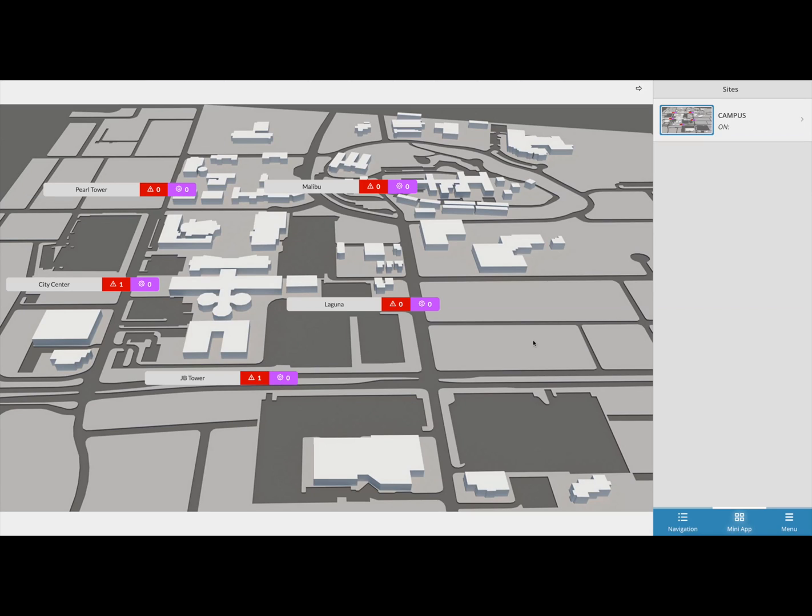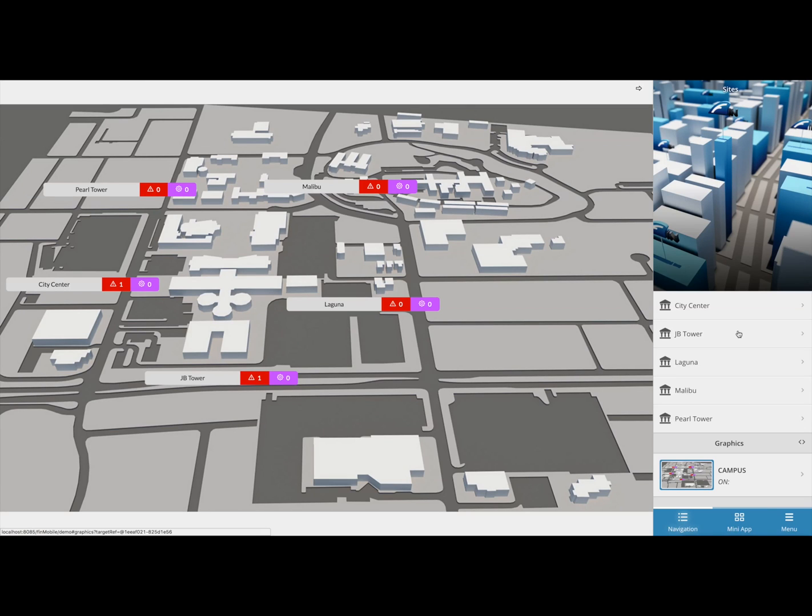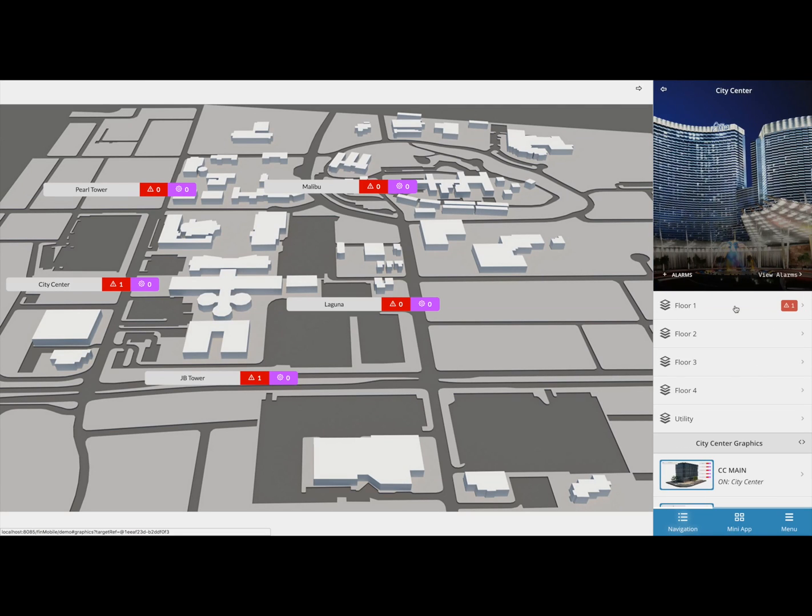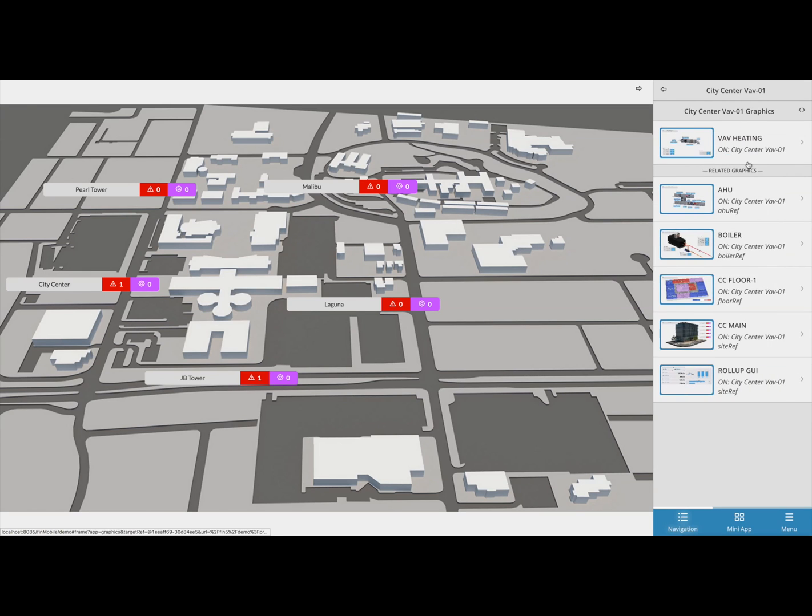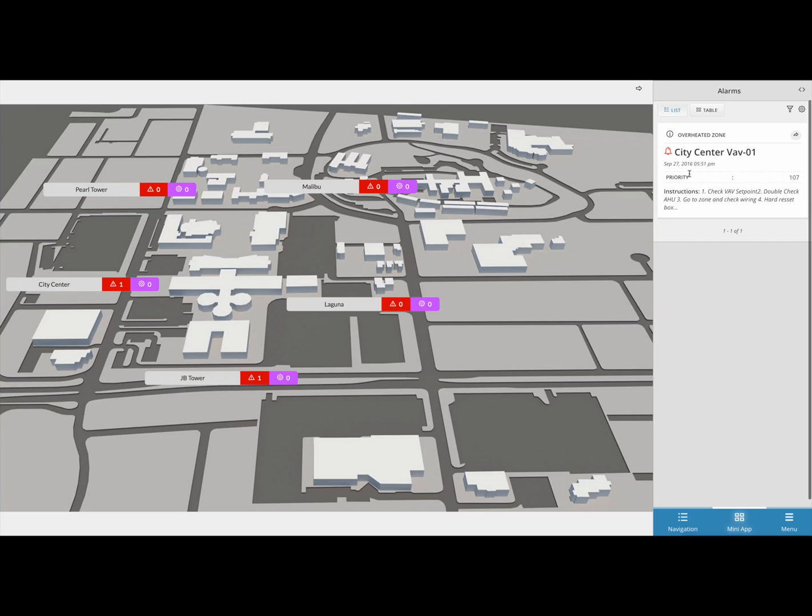To show you the results, if I go down to my VAV1 I can now see that an alarm was thrown due to the room temperature being over 80 degrees for more than five seconds.